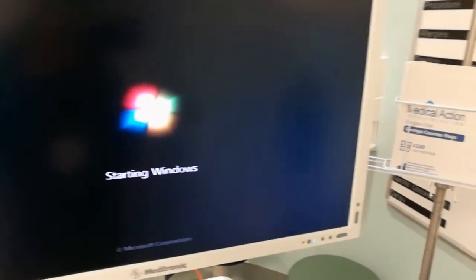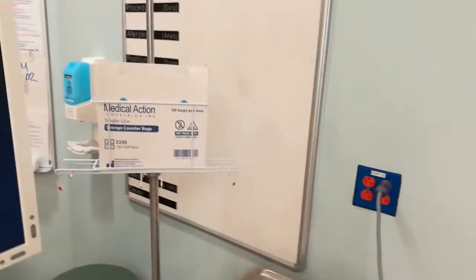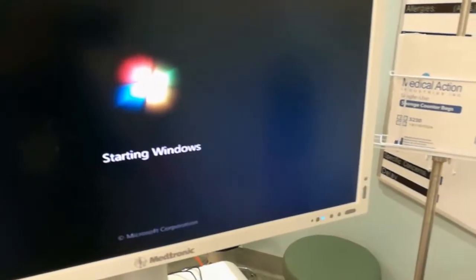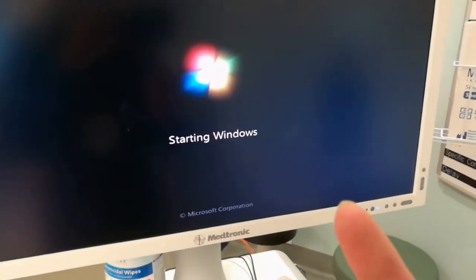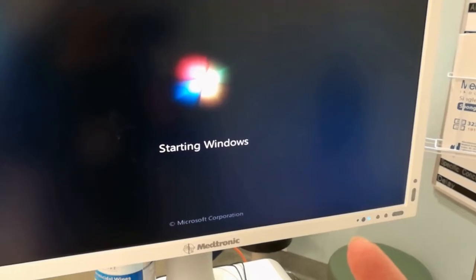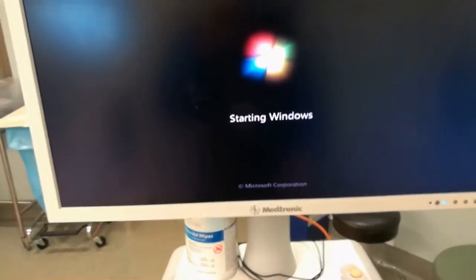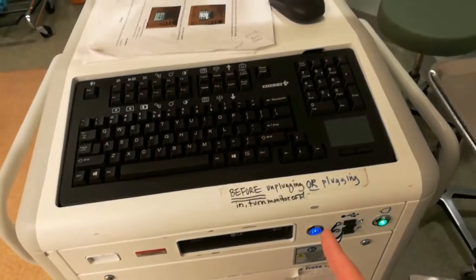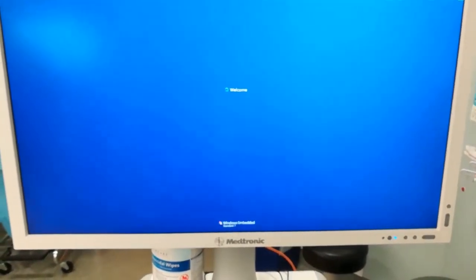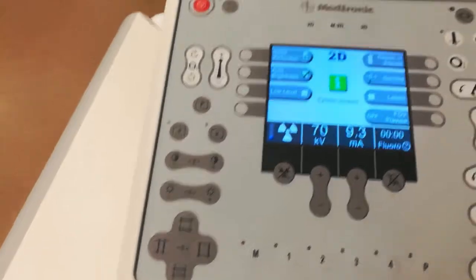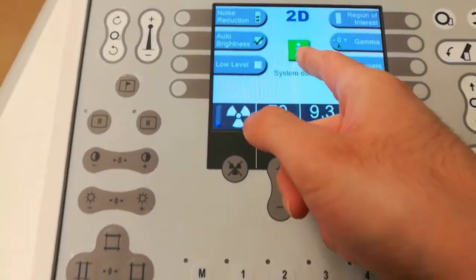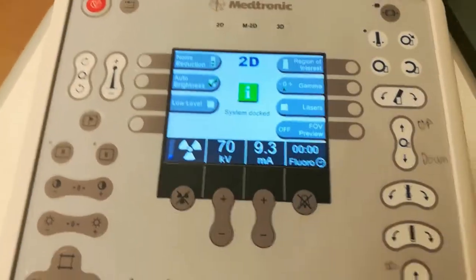So to do the reboot, you can't just say, screw this thing, it's being mean to me, and unplug this thing from the wall because it's taking forever to shut down. Because if you do that, you'll trip the breaker on the monitor and you literally have broken the machine. So if you need to do a reboot, just press and hold the power button again. It will take forever to power off if that's the route it forces you to go, but it'll get there after like 20 minutes. So while we're waiting for the workstation and the rest of this thing to boot, and voila, actually I just finished booting, so green is good on this machine.